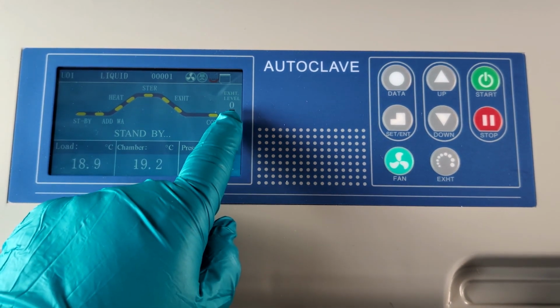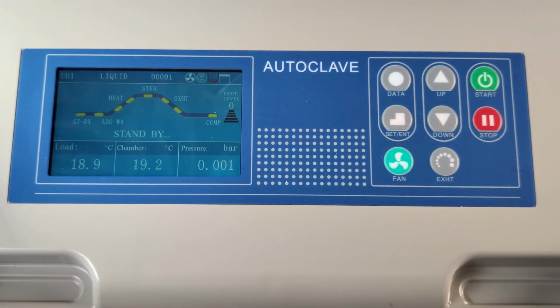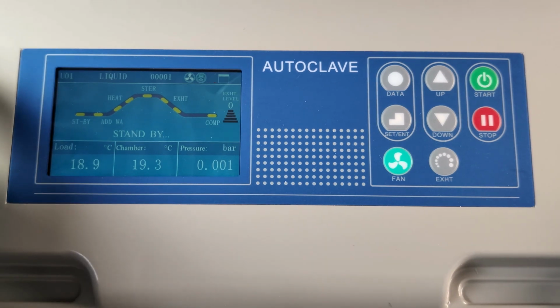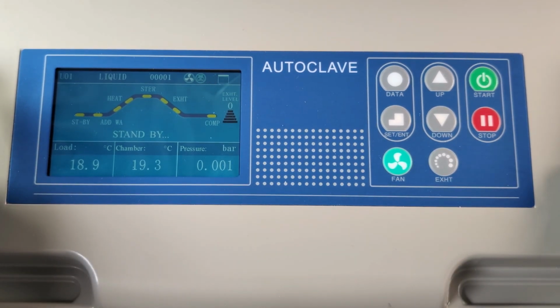But with the exhaust level, you can set the exhaust level on 5 different levels. From 1, which is a slow bleed, so that you're gently exhausting the autoclave, to a much faster rate, depending on how impatient you are. And so you can set the optimum vent level depending on what's most important. So that covers the central part of the autoclave screen.